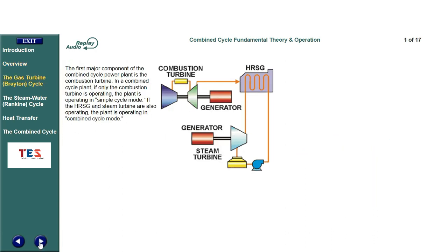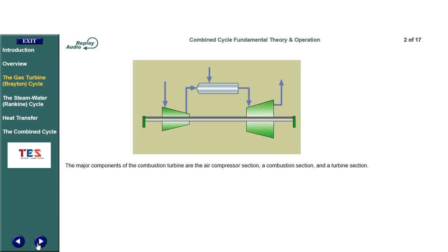The first major component of the combined cycle power plant is the combustion turbine. In a combined cycle plant, if only the combustion turbine is operating, the plant is operating in simple cycle mode. If the HRSG and steam turbine are also operating, the plant is operating in combined cycle mode. The major components of the combustion turbine are the air compressor section, a combustion section, and a turbine section.